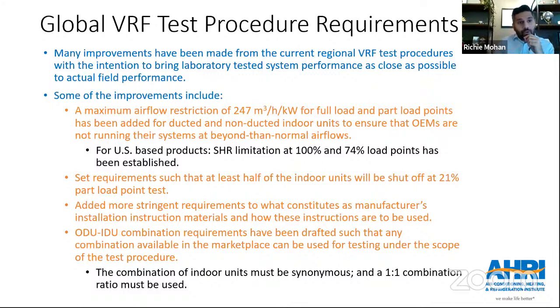And the reason for doing so is because this is what we're going to see in the field. If your load requirement is basically quarter of the full load, then you should be shutting off some of your indoor units. And this is not really how things are done all around today. And I think that will be a good step forward to address this overall issue, as I talked about, which is field versus lab. We've also added in some stringent requirements pertaining to the manufacturer's installation instructions.